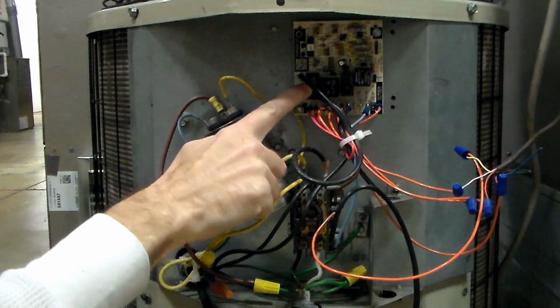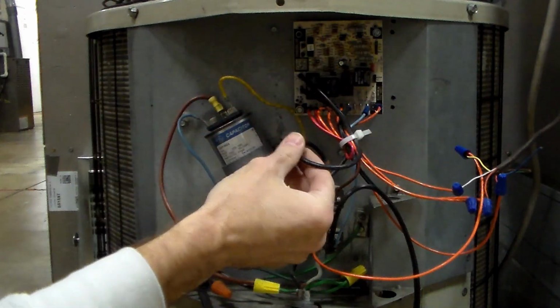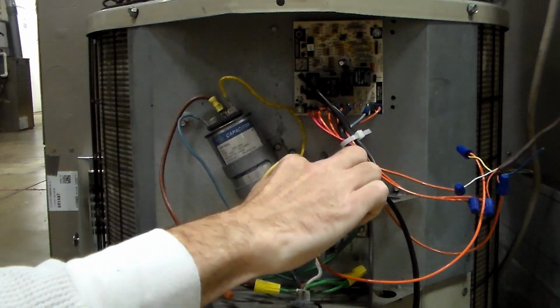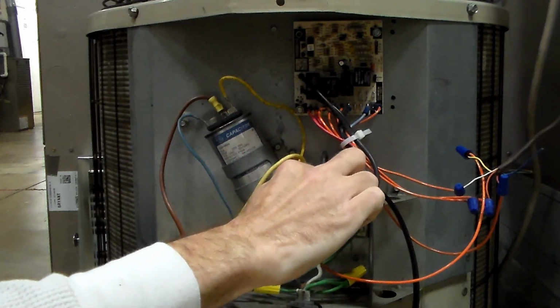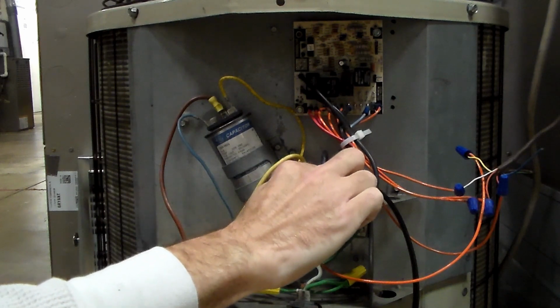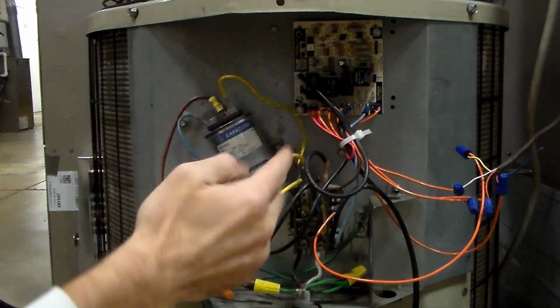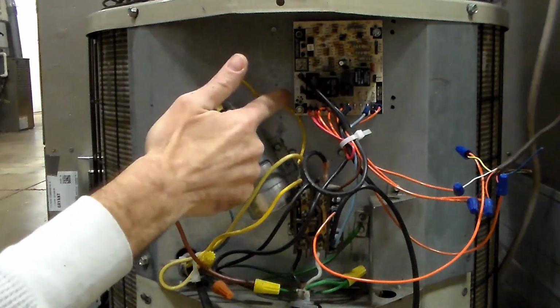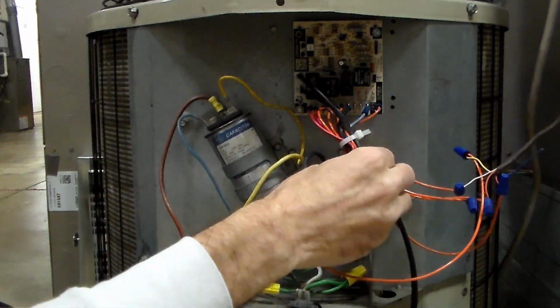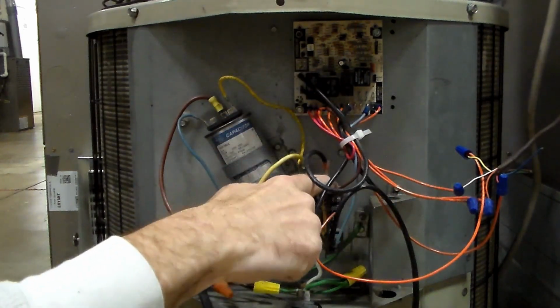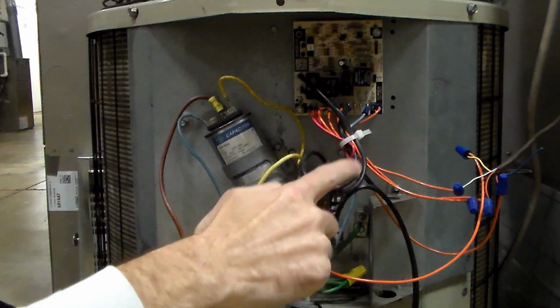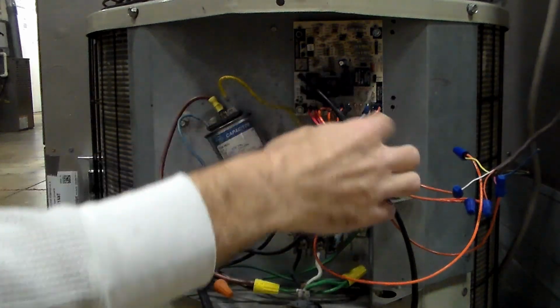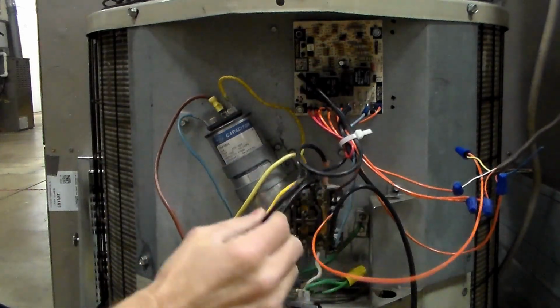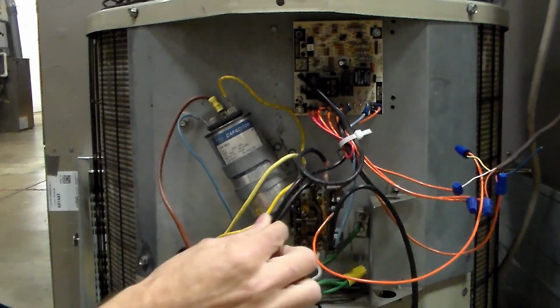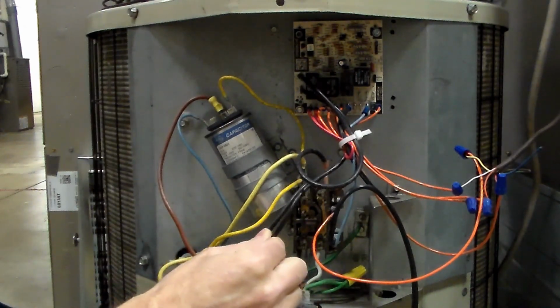So that DF comes off of here, and you can see it comes down to the high voltage lug of the contactor. So it can't be the defrost sensor, because that's low voltage. Knowing how the system works, we have to know that DF2 is coming off power of the contactor, and then it goes through this switch, and then DF1 is actually feeding down here into my cabinet to my condenser fan.